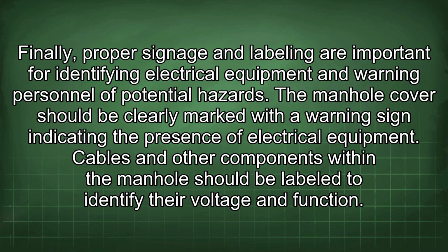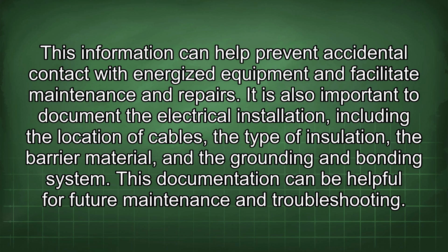Finally, proper signage and labeling are important for identifying electrical equipment and warning personnel of potential hazards. The manhole cover should be clearly marked with a warning sign indicating the presence of electrical equipment. Cables and other components within the manhole should be labeled to identify their voltage and function. This information can help prevent accidental contact with energized equipment and facilitate maintenance and repairs. It is also important to document the electrical installation, including the location of cables, the type of insulation, the barrier material, and the grounding and bonding system. This documentation can be helpful for future maintenance and troubleshooting.